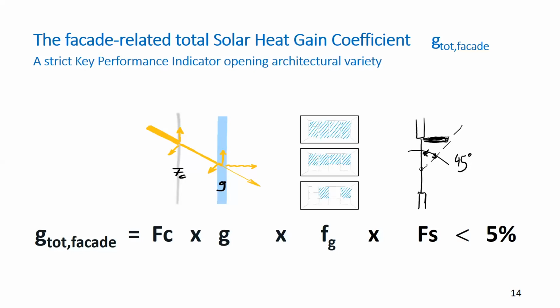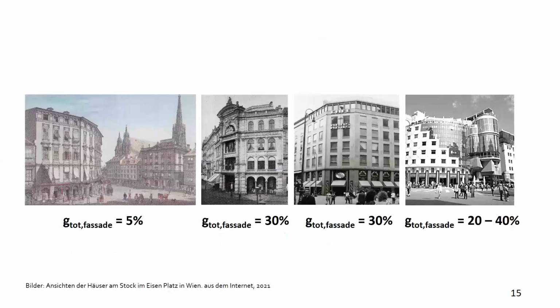And I look at buildings, at real buildings. And I took a very prominent place in the heart of Vienna. You see our St. Stephen's Cathedral in the background. And it's the same buildings, four generations of the same building in a stretch of 300 years. And the first building, you see maybe a facade glazing proportion of 30% or something like this, a single pane glazing with 80% solar heat gain coefficient, outside shading with a shading factor of 20% and no overhangs. And it results exactly in a 5%.